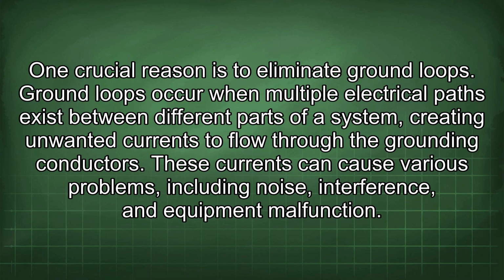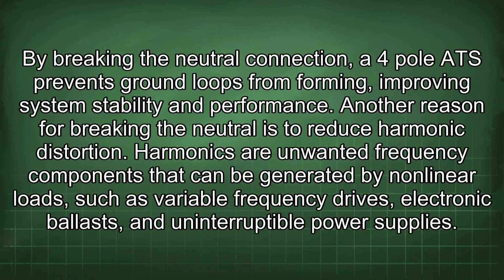One crucial reason is to eliminate ground loops. Ground loops occur when multiple electrical paths exist between different parts of a system, creating unwanted currents to flow through the grounding conductors. These currents can cause various problems, including noise, interference, and equipment malfunction. By breaking the neutral connection, a 4-pole ATS prevents ground loops from forming, improving system stability and performance.